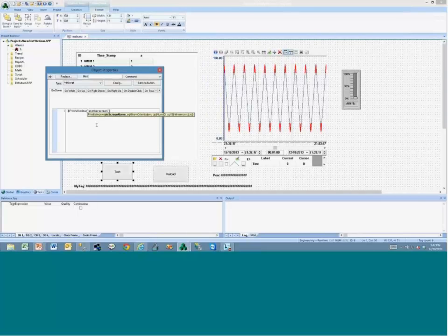What is pretty cool is that you can have a report screen that you don't necessarily want to open on the monitor, but eventually you want to execute this function, PrintWindow, in a button or in a script to, in background, render this screen and send the graphical content of this screen, with tag values, whatever is on the screen, to the printer.